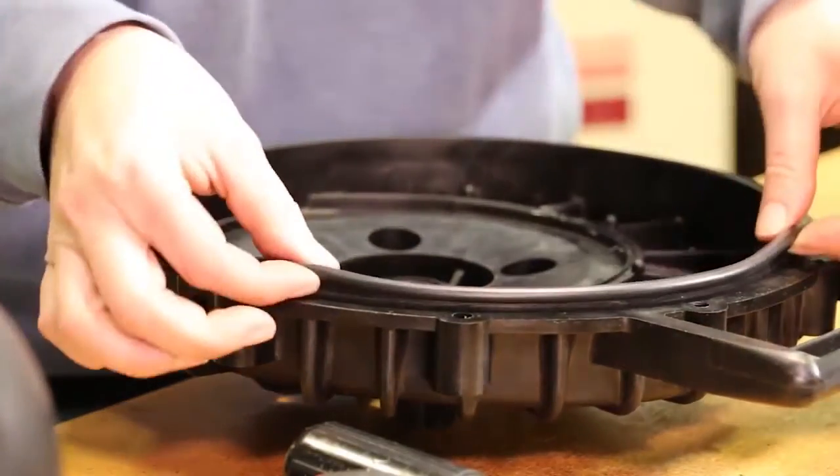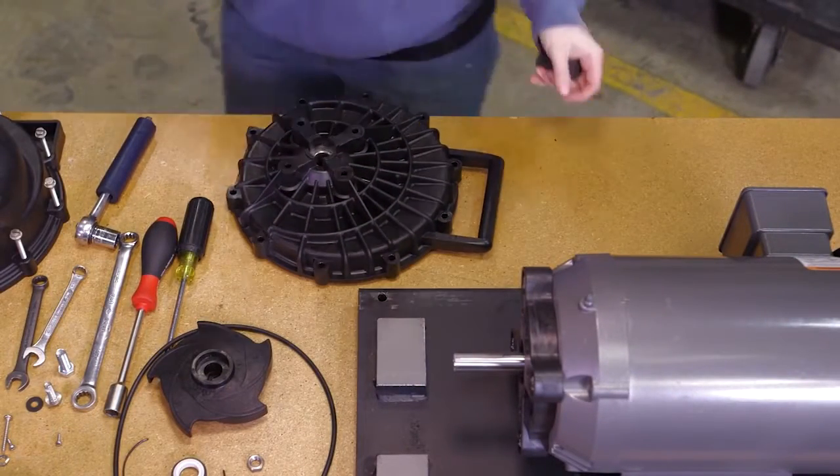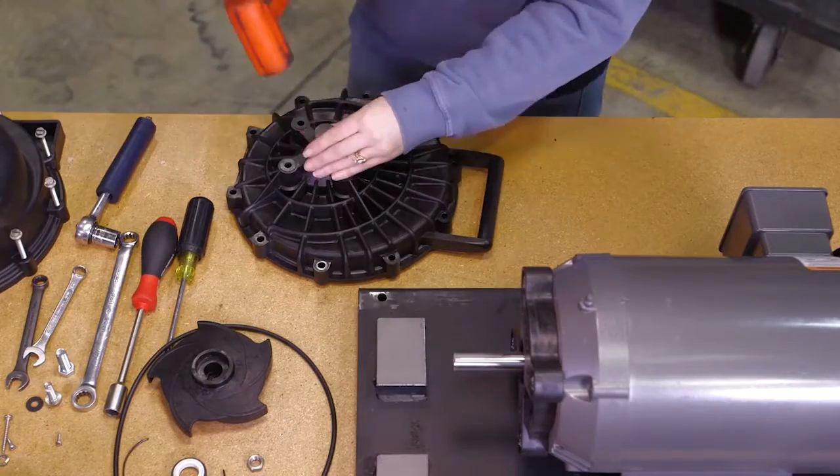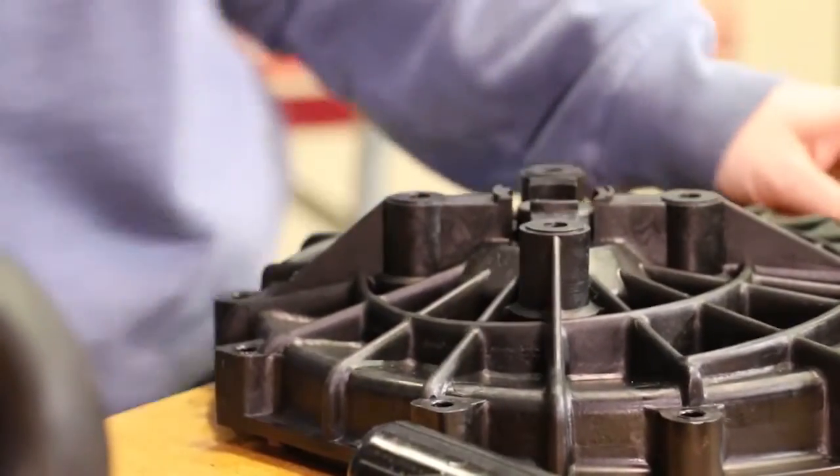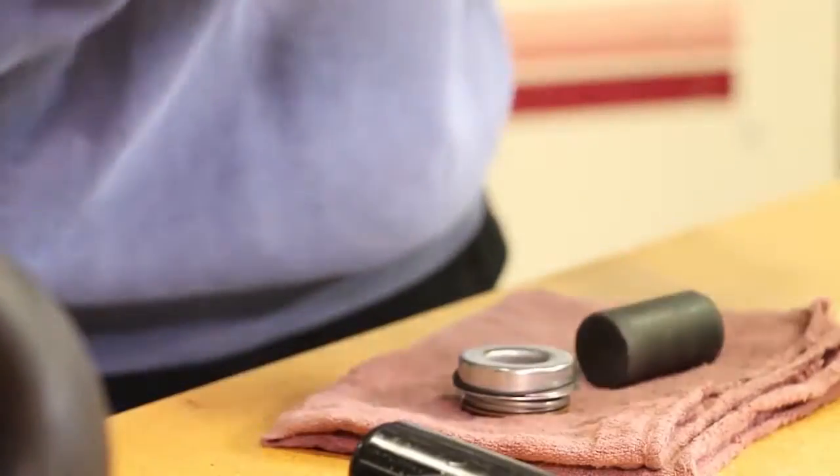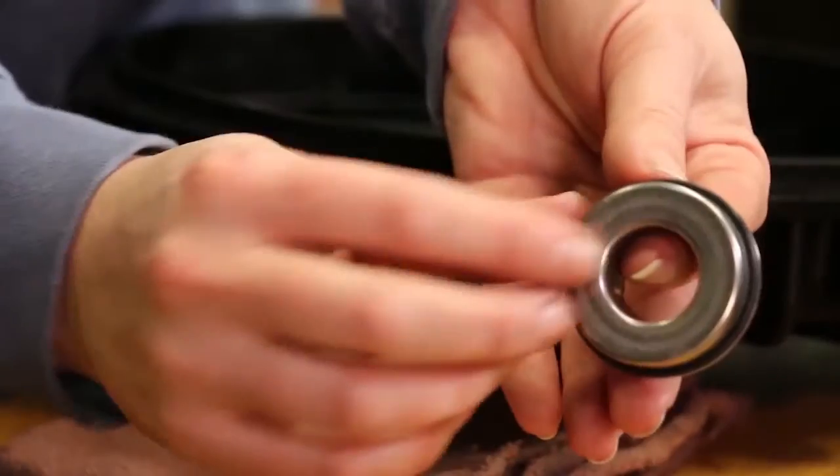Remove the body O-ring at this time. Remove the carbon seal half from the rear bracket. This may be done by using a round object such as a wrench socket and by tapping it gently with a hammer. The seal is very fragile, so take care not to crack the seal if it will be reused. Now, remove the O-ring from seal.